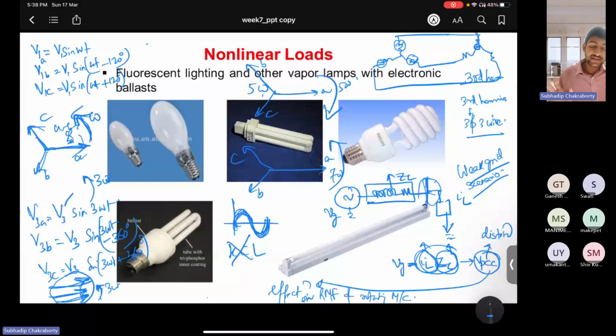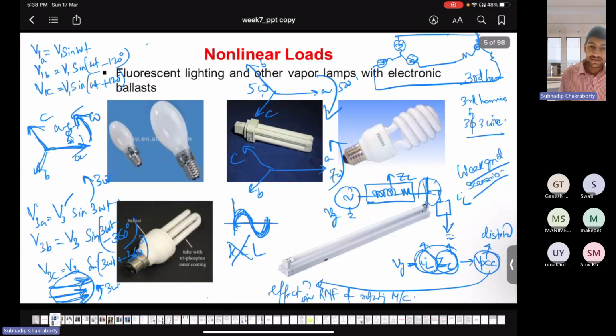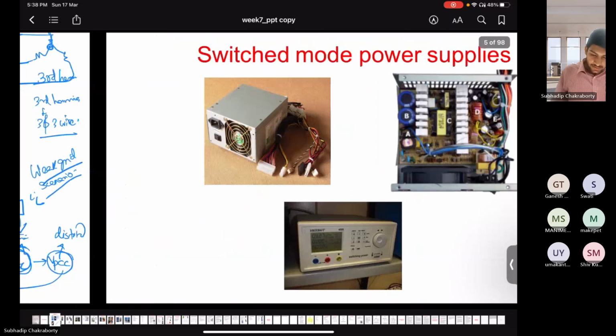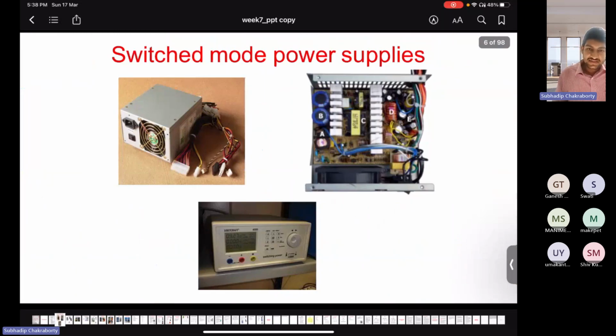So that's why these nonlinear loads have quite a large potential, and they can do much damage to those electromechanical systems. And also you have some oscillations in the machines which may lead to power system instability. That is very common, because in the normal situation also, due to the imbalance and mismatch between the generation and the load demand, you have such low frequency oscillations. Now due to the presence of these nonlinear loads, these oscillations become more prevalent, and this oscillation translates from one synchronous machine to another synchronous machine, and this can lead to full collapse of the power system.